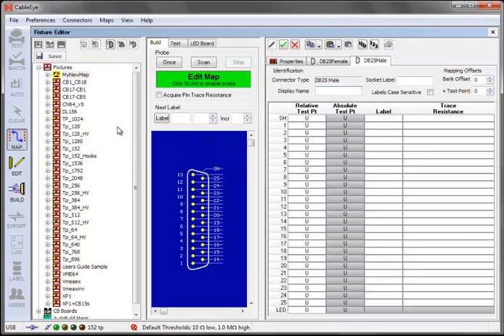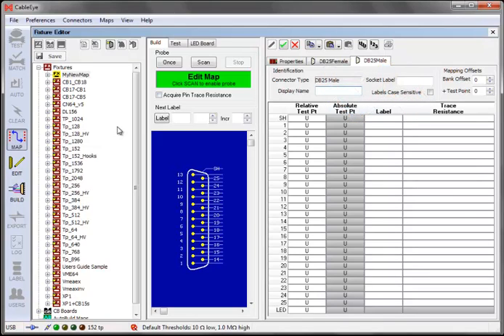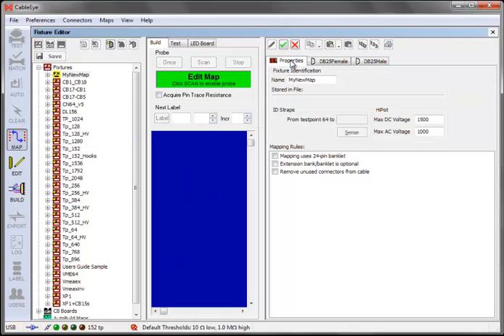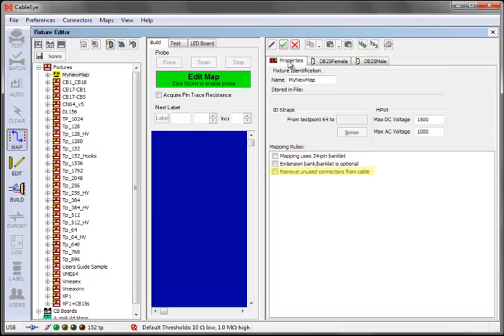On the rightmost pane, you'll see a set of tabbed windows. There's one tab for each connector you added, and a Properties tab that contains information about the entire PinMap. If we briefly look at the Property tab, we'll see some mapping rules checkboxes. The first two items apply only if you have expansion units, and indicate what to do with the 24-pin bank on the base module. In general, you can ignore these. Check the third item, Remove Unused Connectors from Cable, if you want CableEye to remove connectors that exist in the map, but to which nothing was connected when you acquired test data. By default, CableEye includes all map connectors in your test data, whether anything was connected to them or not. The HiPot parameters impose maximum voltage limits when using this interface with an HVX model tester.